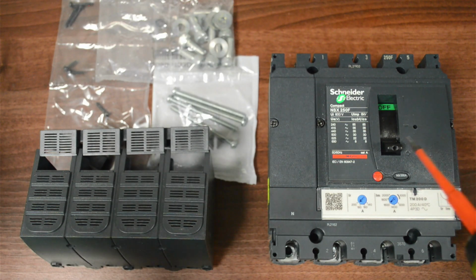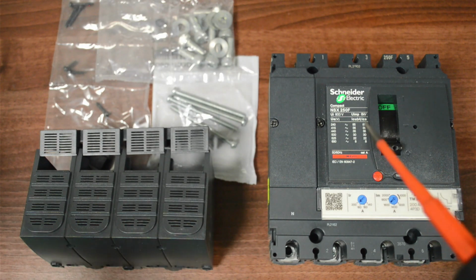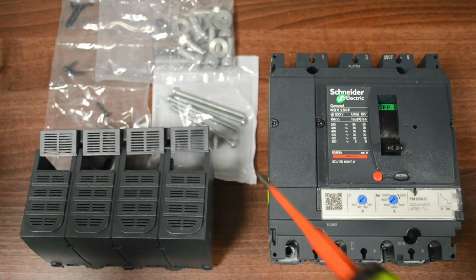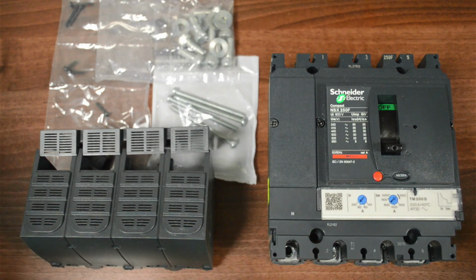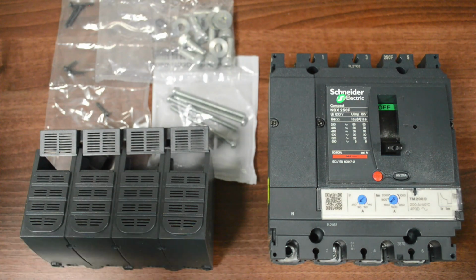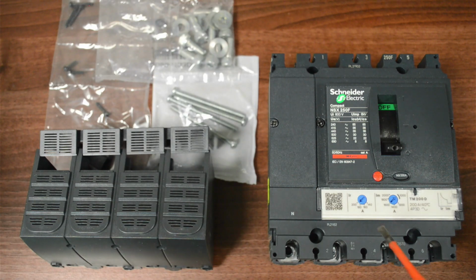You can still get cage clamps on your MCCBs where you would wire in the cable directly without a lug, but usually that's what you find, and you have your bolts and your washers over there to enable you to do that. You've also got these little cable trays here, so the cables run through inside here, just to give a little bit of further protection again inside the distribution panel board, so you're protecting yourself. Just to talk a little bit about these dials then, and then we'll go through some of the unique features of the Schneider product.